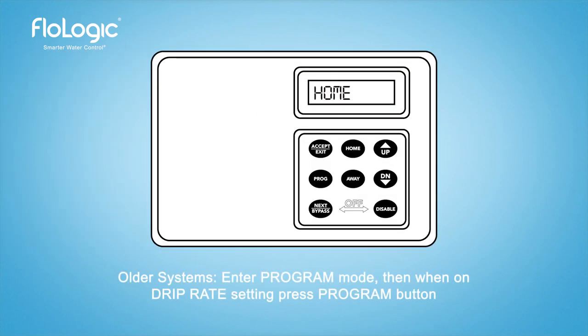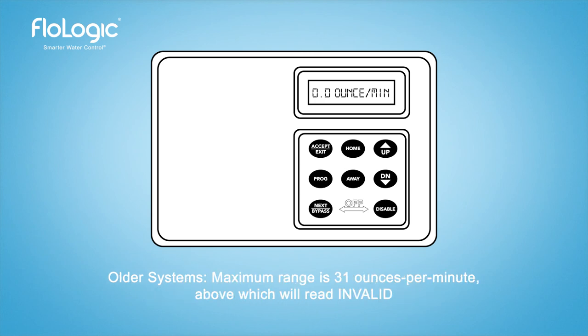To see the real-time flow rate when the system is in the home mode, press the home button to display any flow occurring from a half ounce up to 48 ounces per minute. Flow occurring above 48 ounces is indicated by the words high flow.